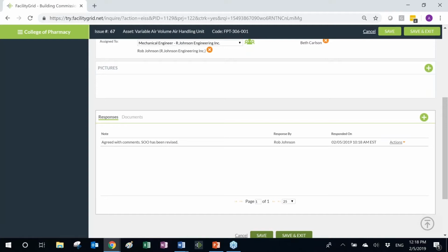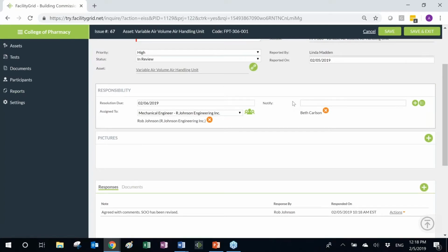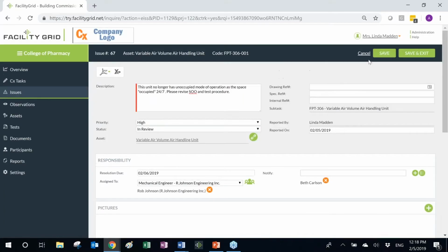And now, since the contractor has originated the issue, the contractor can review the new sequence, can review the response of the commissioning agent, make sure that his or her programming matches those two documents, and then close this issue. Once the issue is closed, the commissioning agent will be ready to get to the job site and perform the functional testing.